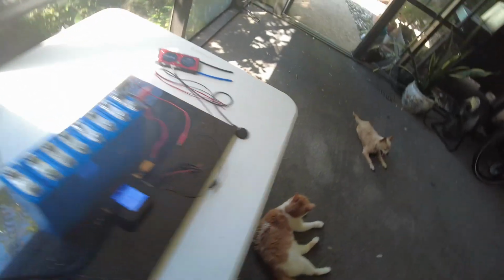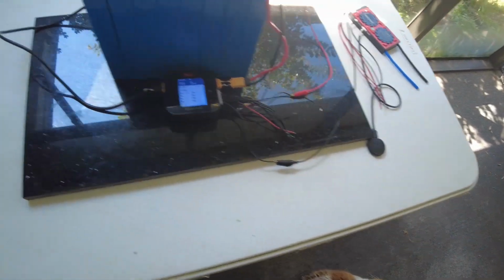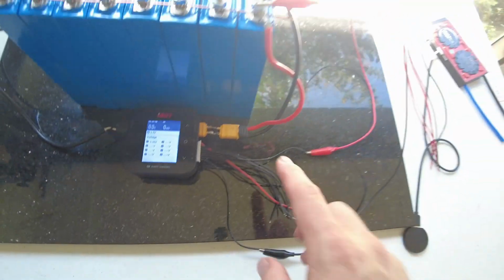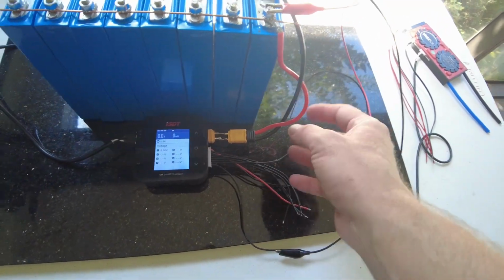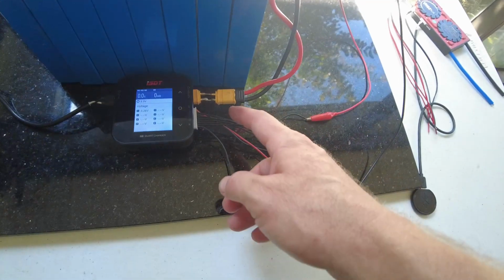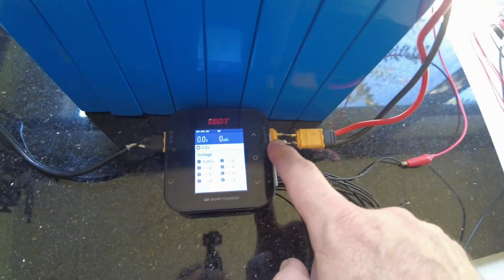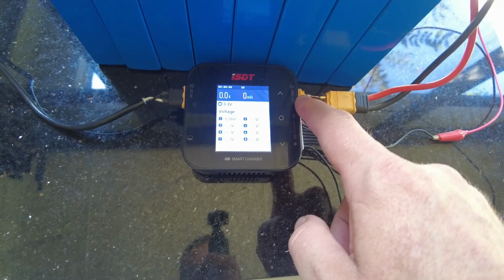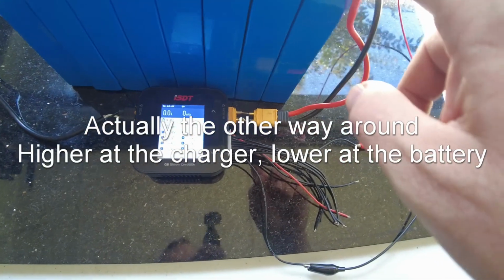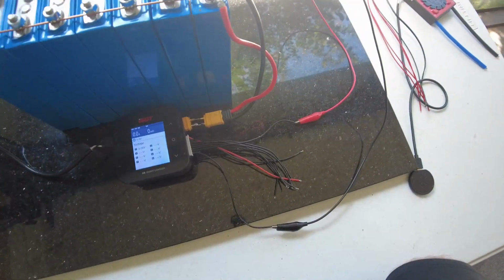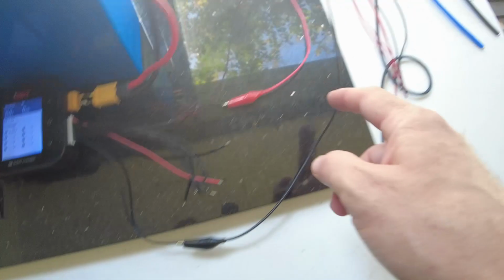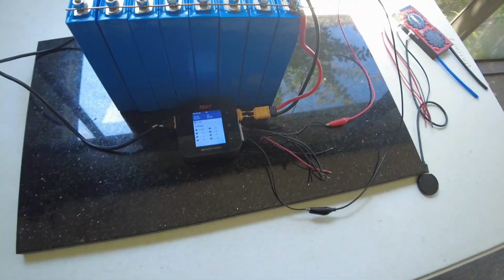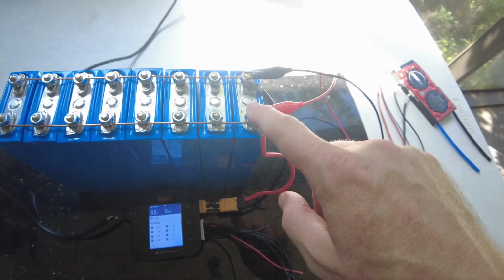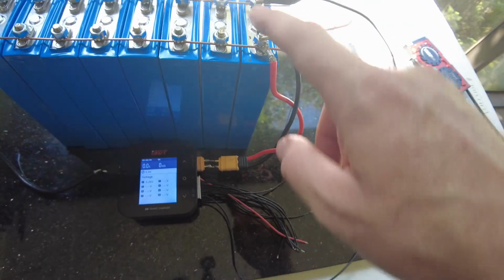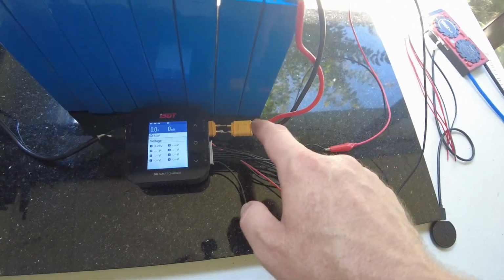The reason you do that is because when it's charging, it's pushing a lot of current through the main cables, and that's going to cause a voltage drop. So when it's trying to read the voltage level, it'll be higher here and lower there, and it won't get an accurate reading. So you use these sense leads, just like your BMS does, so it can check the voltage at the battery without that voltage drop.